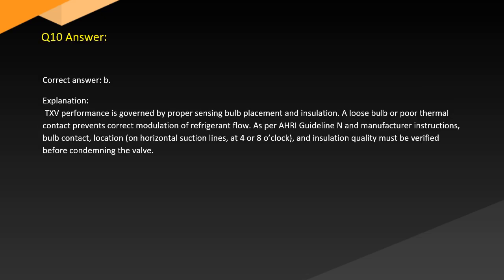Answer. Correct answer: B. Explanation. TXV performance is governed by proper sensing bulb placement and insulation. A loose bulb or poor thermal contact prevents correct modulation of refrigerant flow. As per RSES guidelines and manufacturer instructions, bulb contact location on horizontal suction lines at the 4 or 8 o'clock position and insulation quality must be verified before condemning the valve.